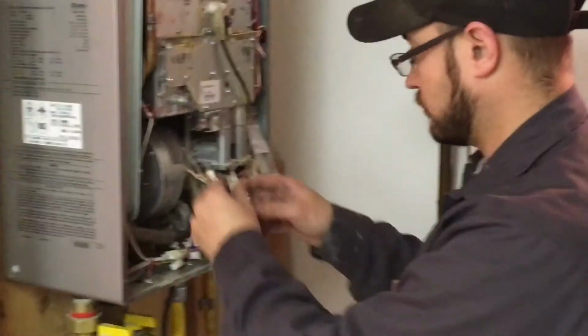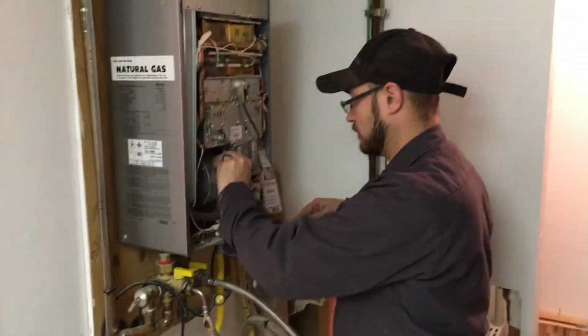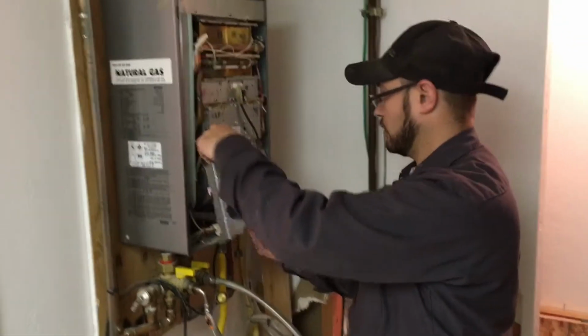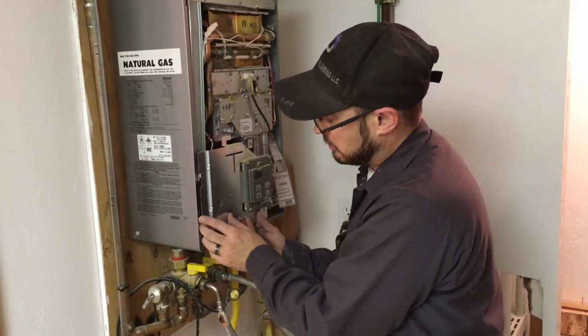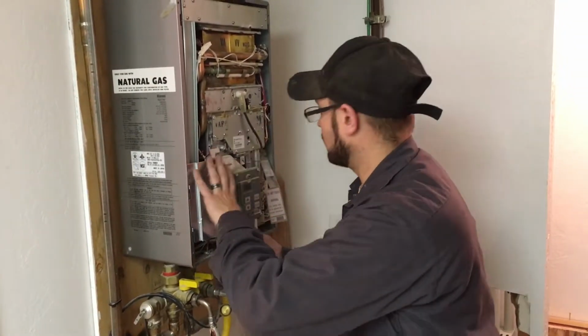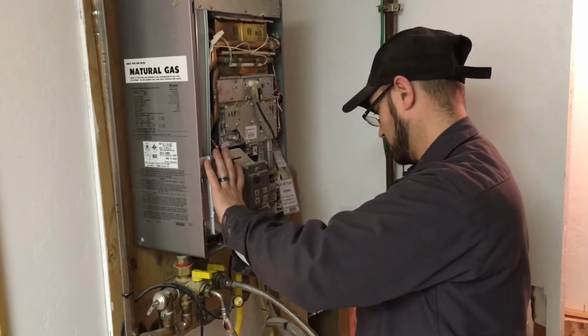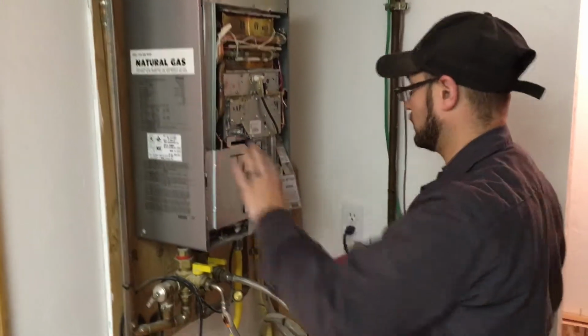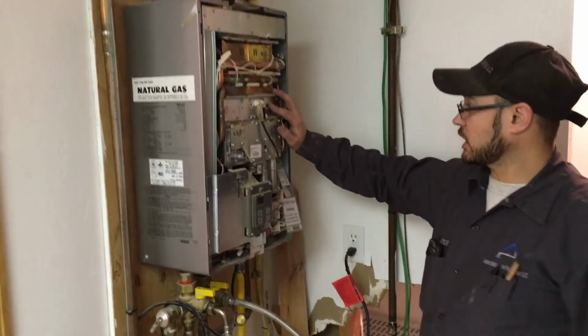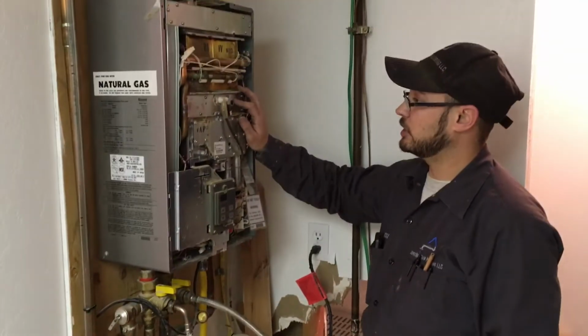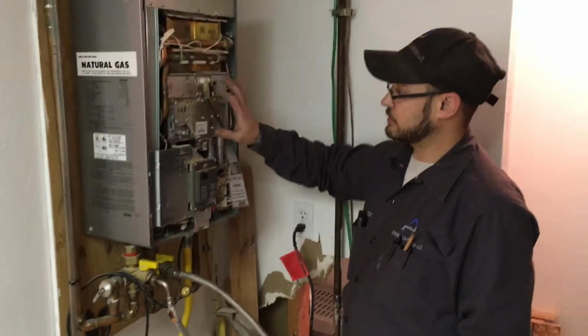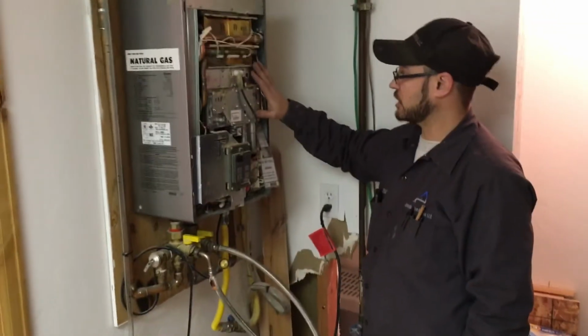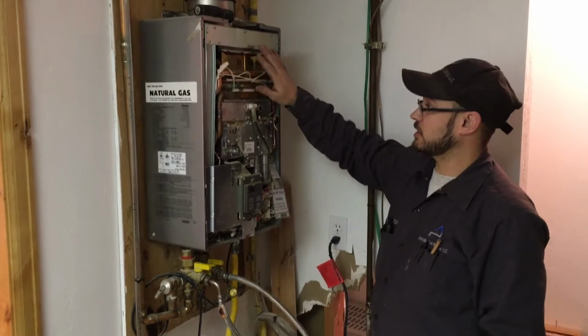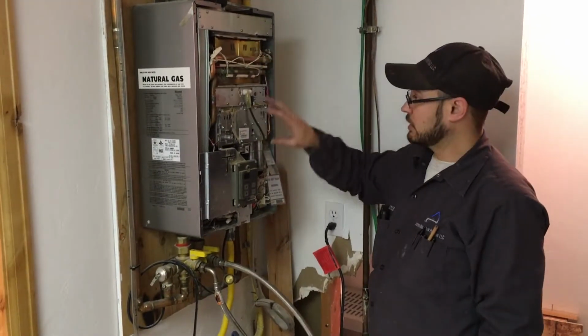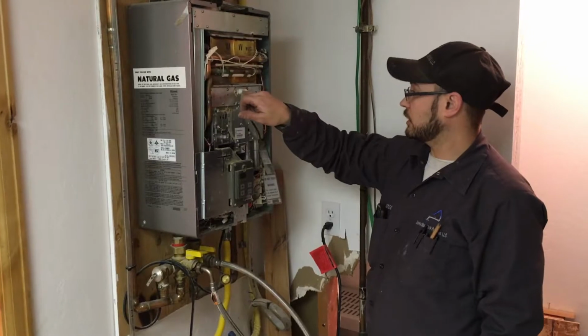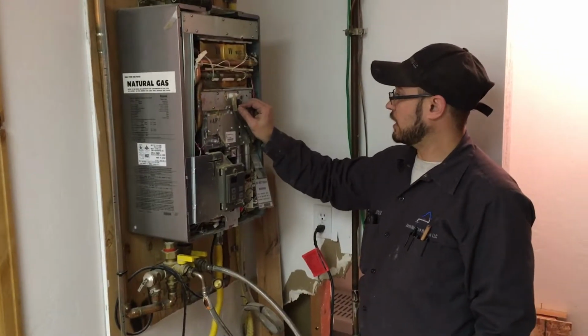We'll go ahead and take our plug, which we unplugged, and plug it back in, then put our control board back in. It just slides in there like that, so there's not much to it - that just fits over the top of that. Basically, you've got your sight glass right here for your burner. This is your primary heat exchanger, where it initially gets hot, and then it goes through your secondary, which is what actually increases the temperature. Then you have your flame sensor and your igniter.